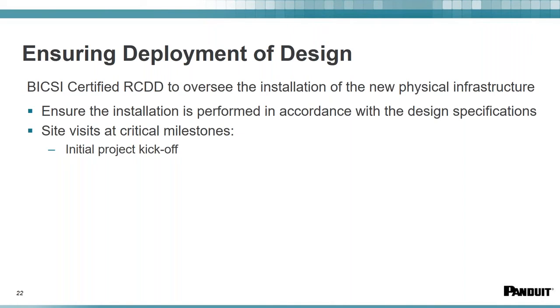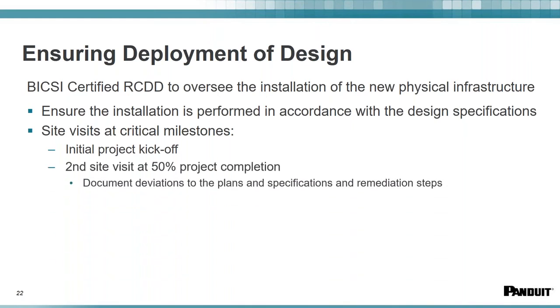So they kick off the project, and in the implementation phase you need to oversee all of this design deployment. Make sure you have planned visits for when certain milestones are met—running the fibers and testing that they're not kinked, checking communication losses on copper, and when you start connecting the control system, that's where you test your program. But before that, you're doing all these visit steps to make sure the architecture you designed is being implemented correctly.